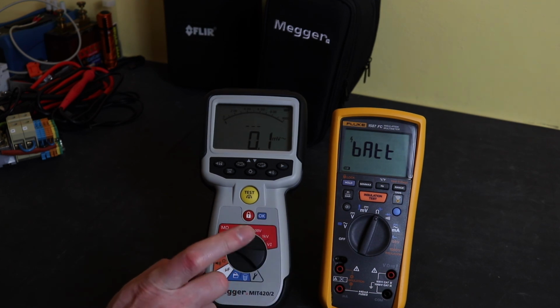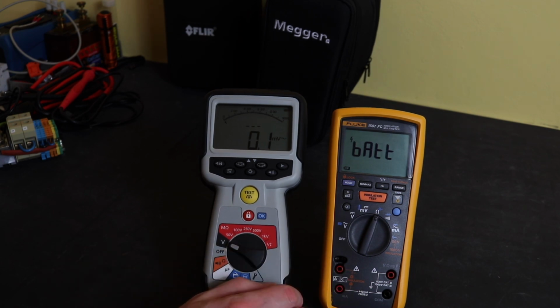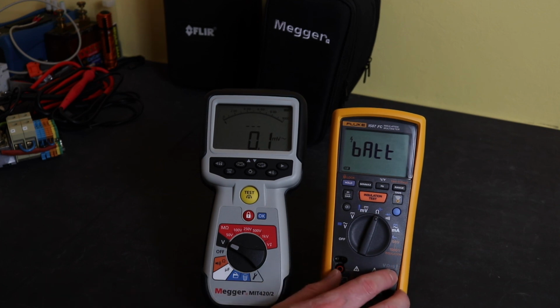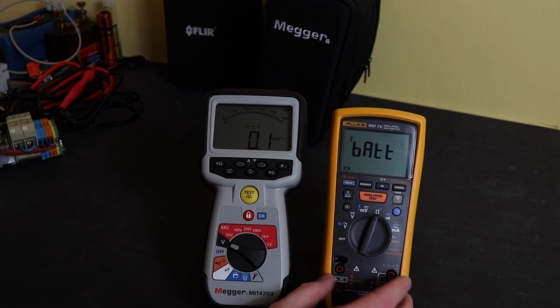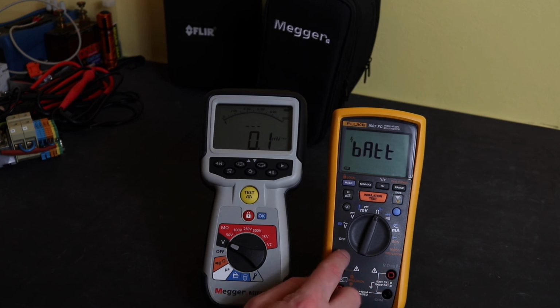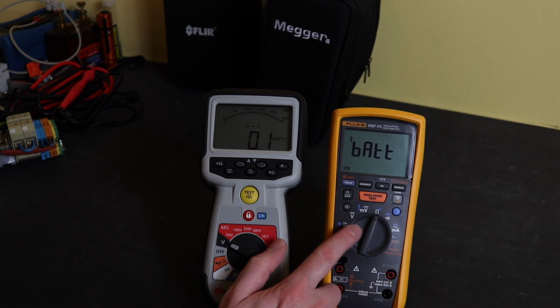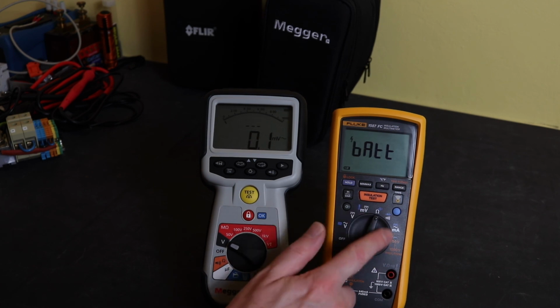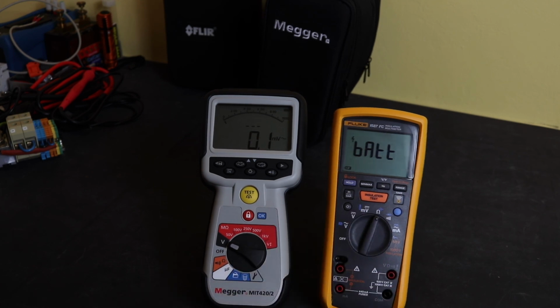On top of that, with its 200 milliamp continuity test function that I need for UK wiring regs, which again the Fluke doesn't have, I would again go with the Megger unit. I guess if you're more into the control and instrumentation side of things and you just want an insulation tester to give a sort of go/no-go test for what you're working on, because you'd much rather have the voltage and resistance and current capabilities of the instrument, I guess that's more where the Fluke would be aimed.